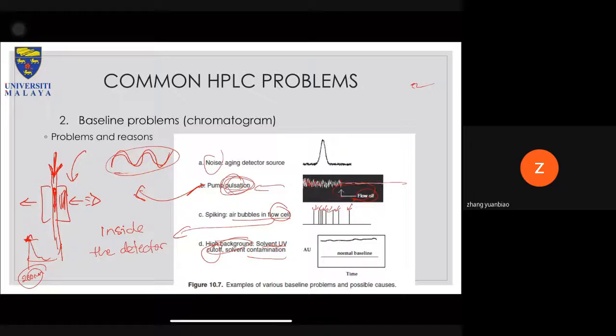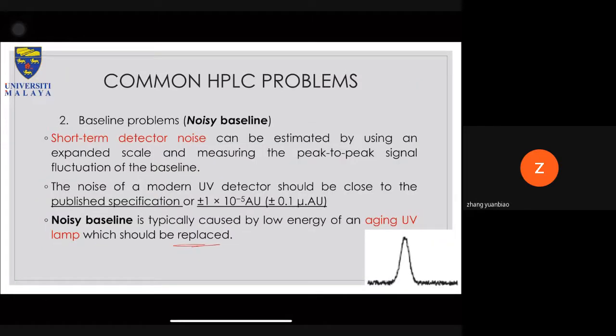Short-term detector noise can be estimated by using an expanded scale and measuring the peak-to-peak signal fluctuation of the baseline. The noise of a modern UV detector should be close to the published specification, or about 0.1 micro AU. Noisy baseline is typically caused by low energy of an aging UV lamp, which should be replaced. Okay, this is just an example of a noisy baseline.